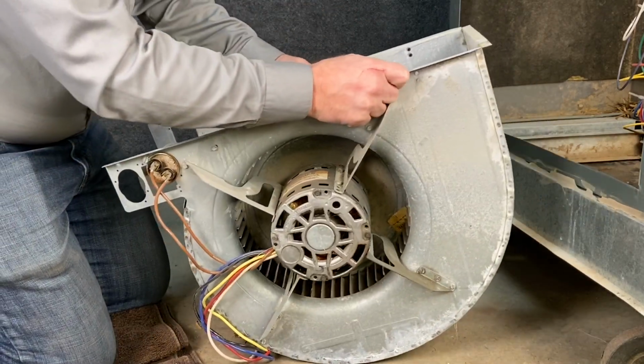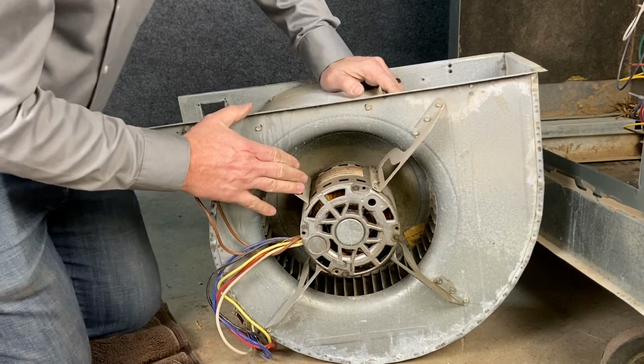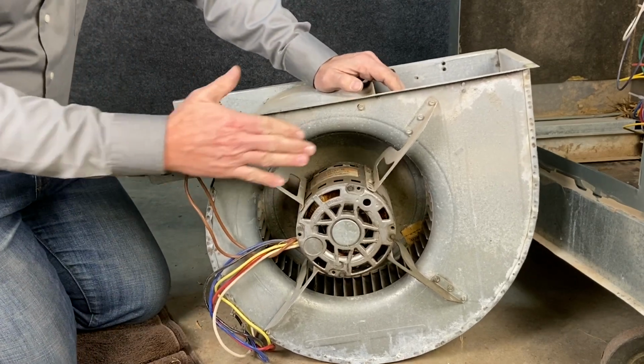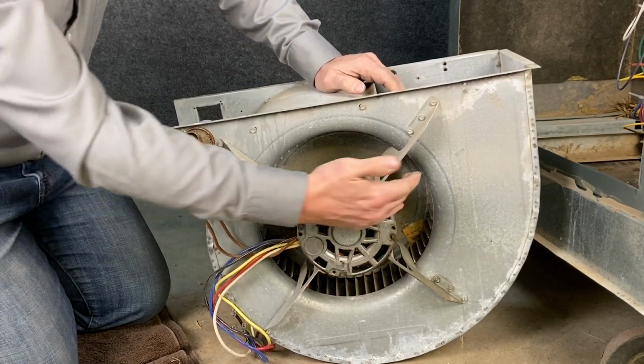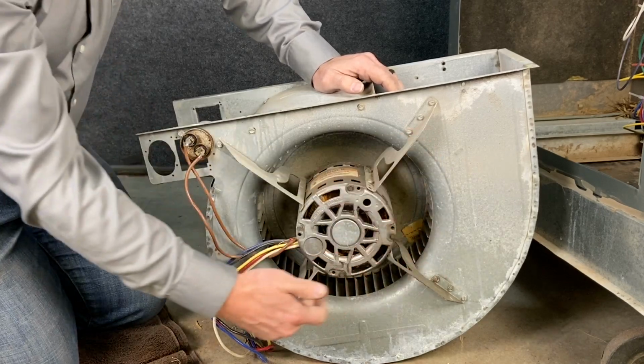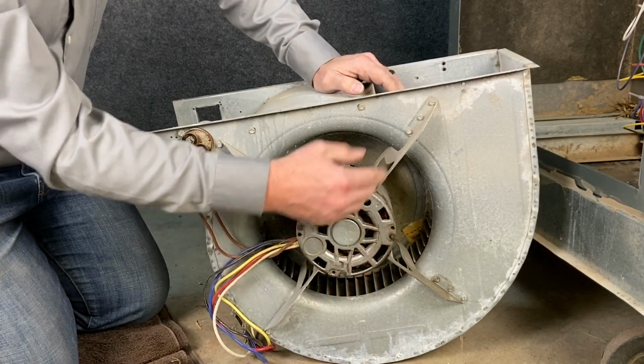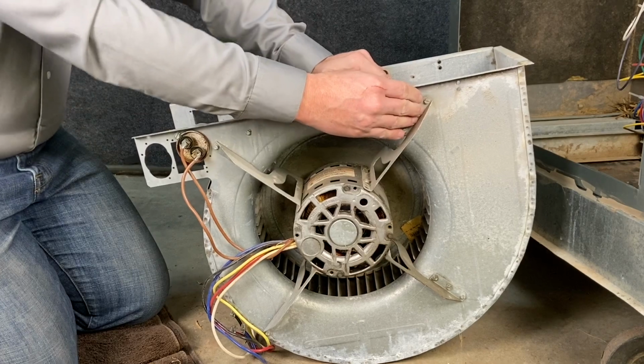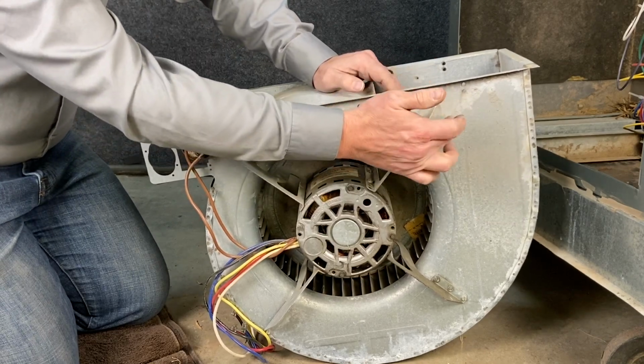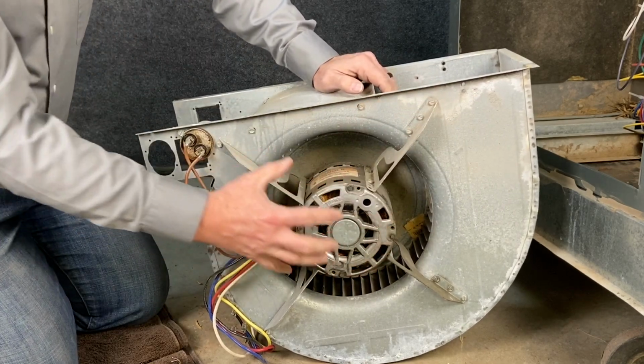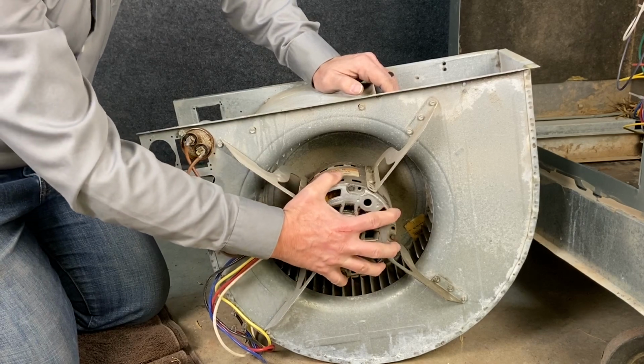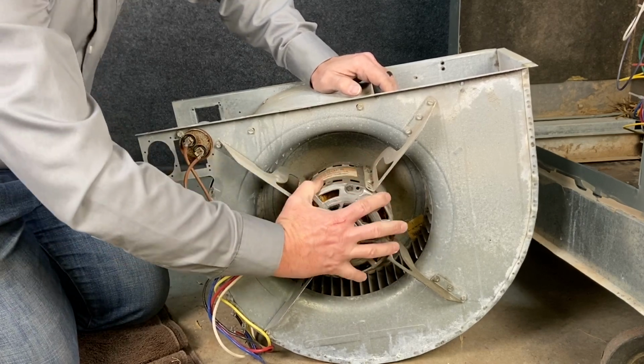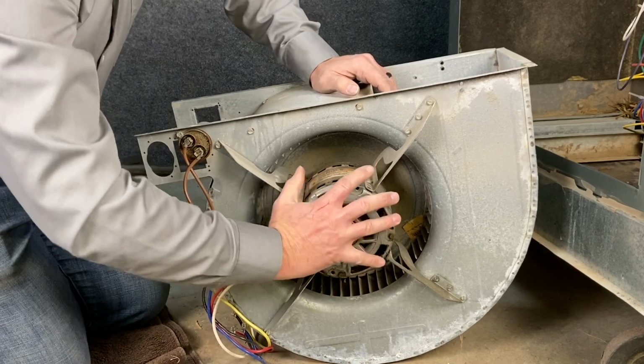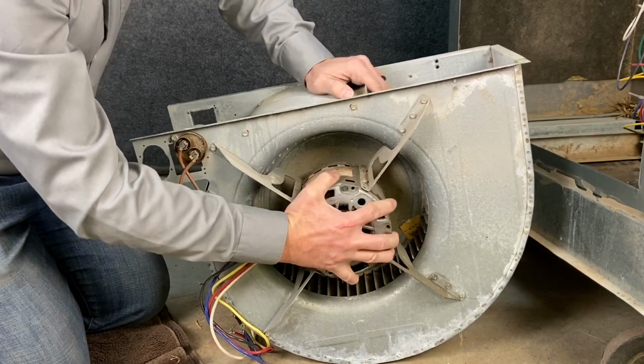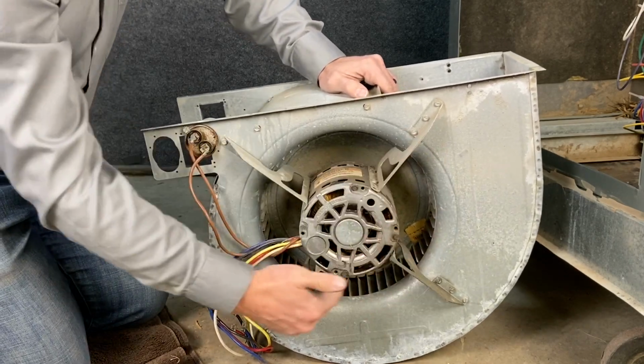Now we're going to look at this other side. This is the only brand I know of, Rheem and RUUD, that does their blower housings like this. And what they use is these thin pieces of metal right here, screwed directly to the motor and directly to the housing. Most units use a type of rubber that connects the housing to a bracket. The idea behind this, and the reason they do that, is this thinner metal allows it to take the shock of the motor. So when this motor first starts up, it allows for this motor to twist some, and this takes that shock out of it.